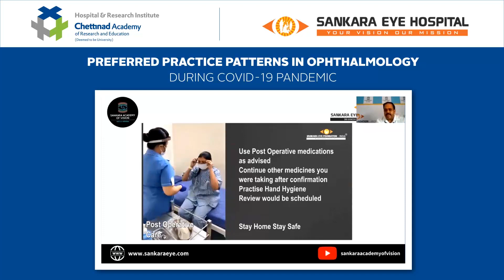If you have shut down your OT and you're looking to restart your OT, this is something that we did across our Sankara hospitals before restart. First and foremost, your air handling units need to be cleaned and disinfected. You may need to repeat your microbial surveillance, the 3 cultures negative, because this is considered to be a long shutdown, as you shut down for about 40 days.